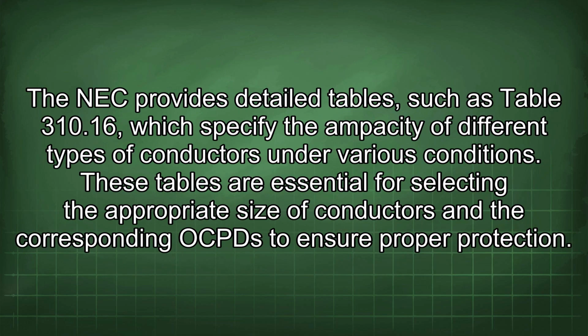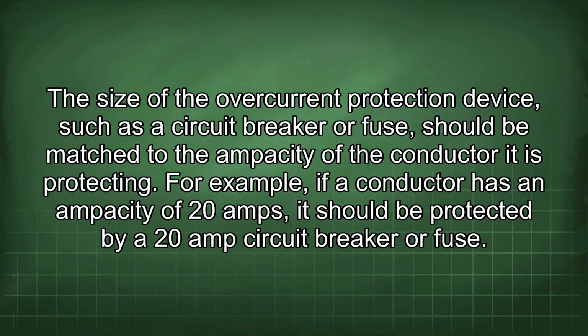The NEC provides detailed tables, such as Table 310.16, which specify the ampacity of different types of conductors under various conditions. These tables are essential for selecting the appropriate size of conductors and the corresponding OCPDs to ensure proper protection. The size of the overcurrent protection device, such as a circuit breaker or fuse, should be matched to the ampacity of the conductor it is protecting.